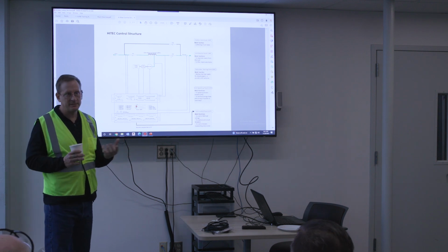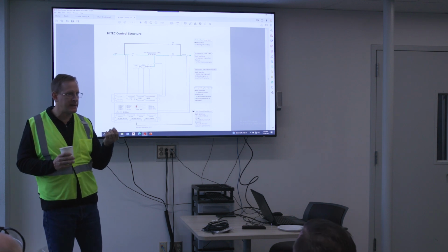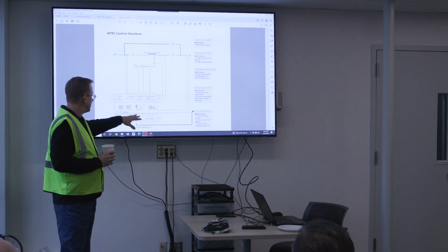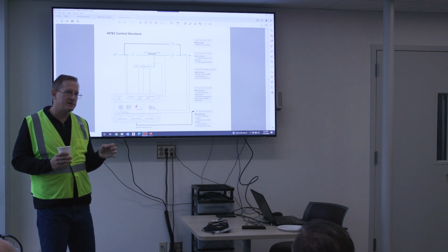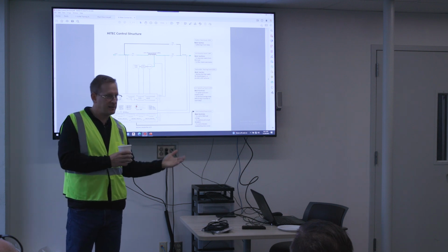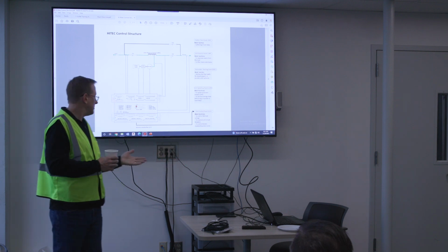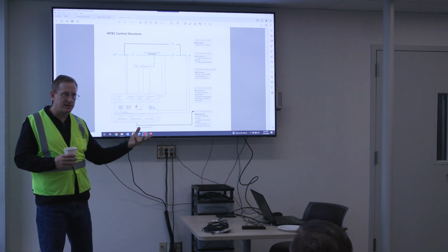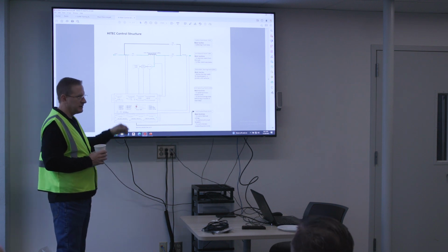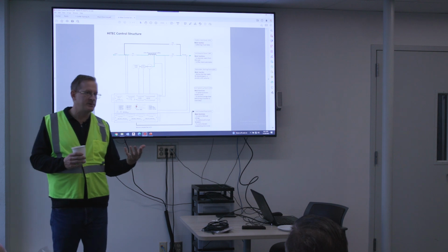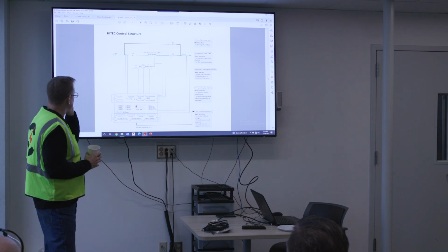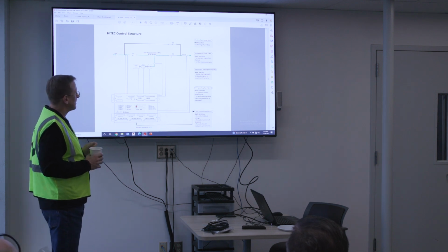So it's a green light. If the mains voltage light is lit, you know that the mains voltage is good. Same with frequency. It's got lights for output as well. It's got lights for synchronization. So you can actually look at the Dicon and tell right away, is it synchronous to mains? Let's say it's coming back after an outage. You can see where it's actively synchronizing to the mains and it's in sync. So again, it's a helpful thing to look at if you know what to look for, and you can get some clues from what the Dicon is seeing just based on those indications on the front of the device. Okay, and I'll show you those when we take our walkthroughs.